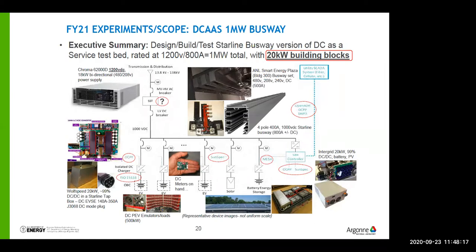This busway you see on the right, this thing that looks like a big door rail hanger, is called busway, used in data centers. It has 4 poles good for 400 amps each, or a 2-pole system I can run at 800 amps at 1,200 volts. To be technical, it's only rated at 1,000 today, but I'm going to run it at 1,200. That gets me a megawatt.